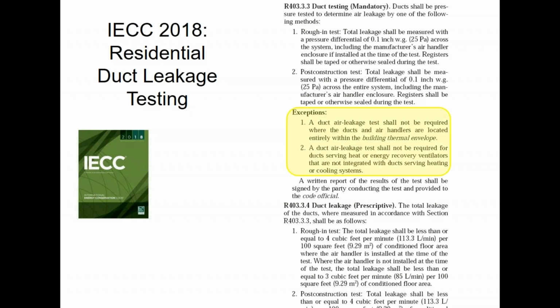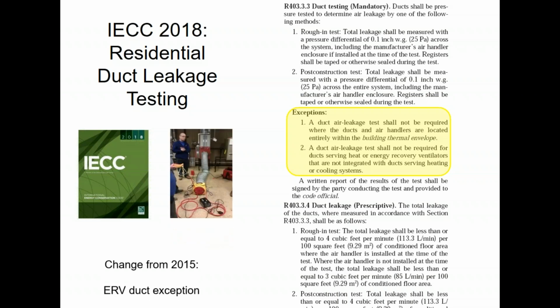It has to be pressure tested to prove that it gets down to a certain leakage rate. The leakage rates are pretty aggressive. You either get 3 CFM or 4 CFM per every 100 square feet of floor area. The 3 versus 4 number: the 3 number would be if your air handler, i.e. your furnace, is not yet installed.